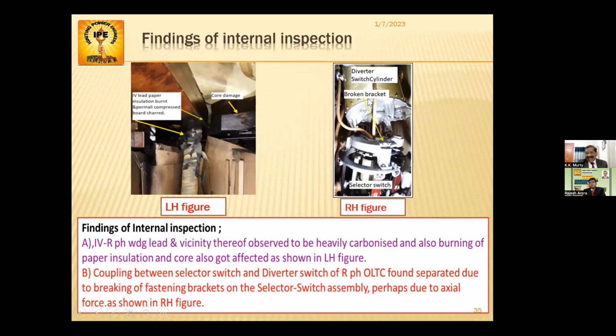It is in a cylindrical form which goes in the transformer, but the oil of diverter switch cannot be mixed with the oil of the transformer, whereas the selector switch is within the oil of the transformer. So coupling between the selector switch and diverter switch of R phase OLTC found separated due to breaking of fastening brackets of the selector switch assembly, perhaps due to axial force as shown in right hand figure.